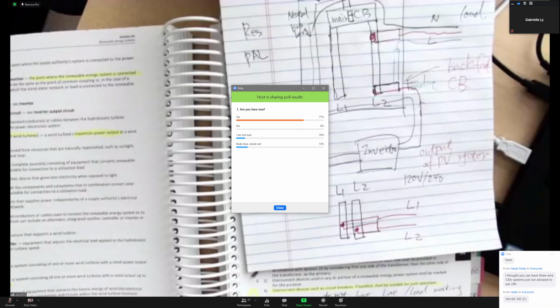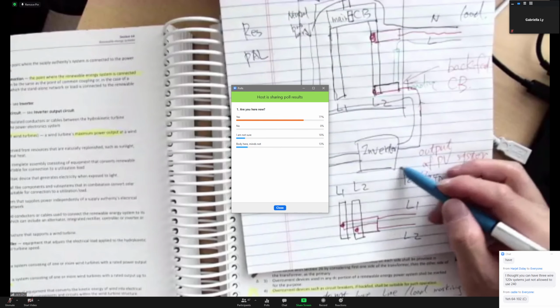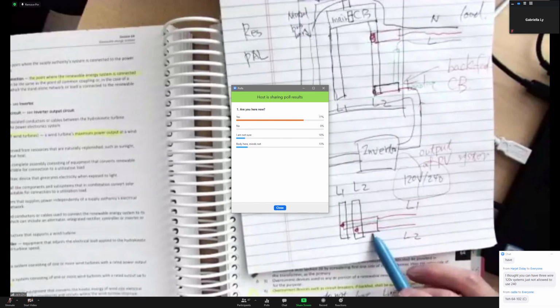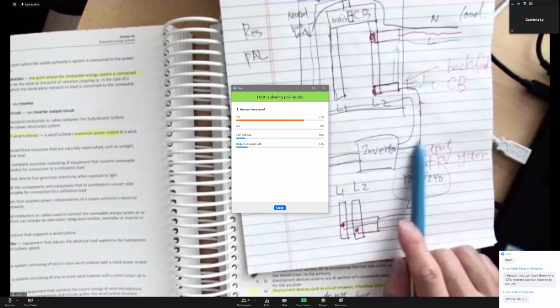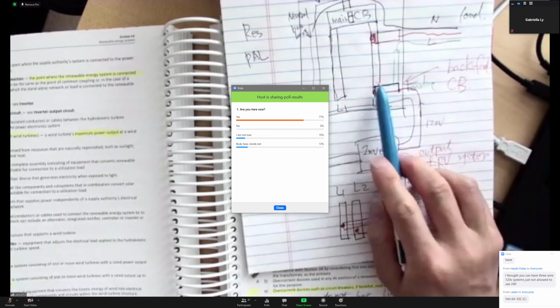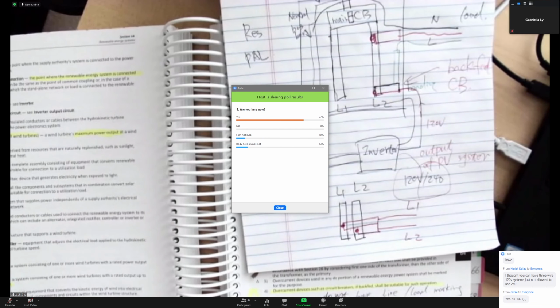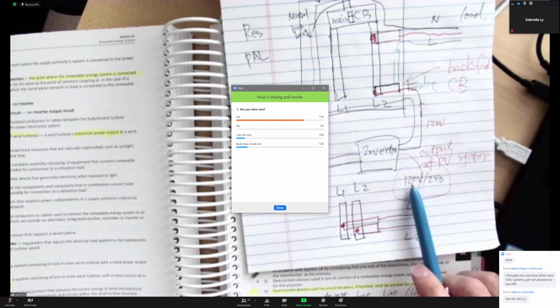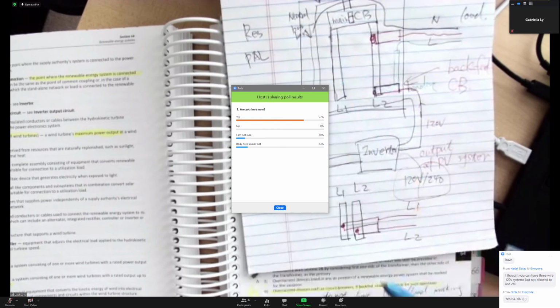It depends on the situation. So if your inverter can give you that, then you can have those double pole circuit breakers connected there. But if your inverter only has 120 out, you can only connect onto one side. Or I think the code says you're allowed to have this kind of connection, even if you only output 120 volts, but you cannot have 240 volts in this panel.